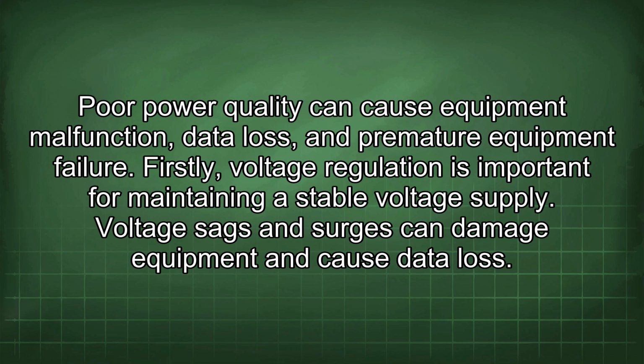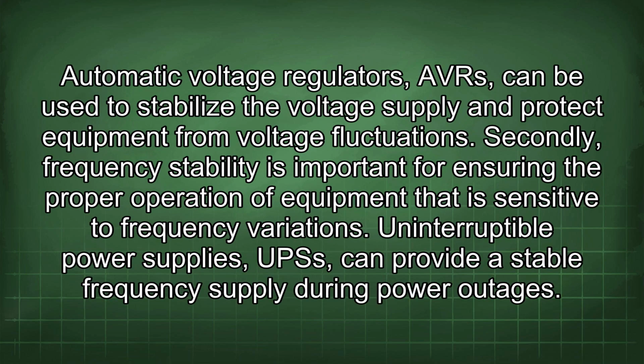Voltage sags and surges can damage equipment and cause data loss. Automatic voltage regulators, AVRs, can be used to stabilize the voltage supply and protect equipment from voltage fluctuations. Secondly, frequency stability is important for ensuring the proper operation of equipment that is sensitive to frequency variations. Uninterruptible power supplies, UPSs, can provide a stable frequency supply during power outages.